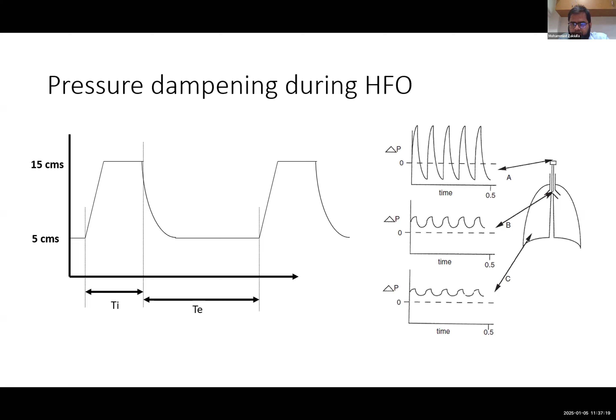Once you have set the delta P on the baby, you have to see the oscillations of the chest. If the oscillations reach from the chest to the umbilicus, that means you are giving adequate delta P. But you always have to confirm with a blood gas within 30 minutes to 1 hour, and then depending on the CO2 values, you again have to adjust your amplitude.